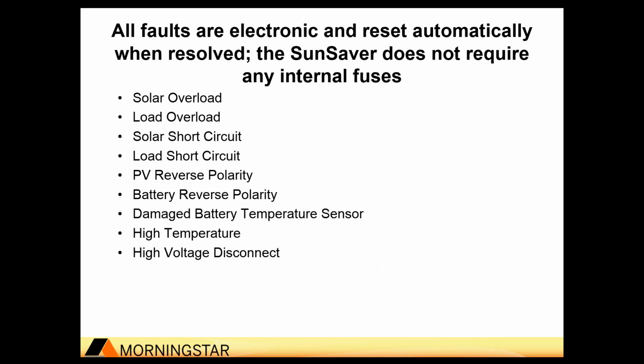Just to detail the electronic protections and emphasize the point that they're all reset automatically. These are conditions that result in a fault of the controller, not some kind of critical error, but a recoverable state. Solar overload, load overload, short circuit protection for both load and solar, reverse polarity on either the battery or the PV, and any kind of high temperature or high voltage disconnect situation. There's really not much that you can do to the Sunsaver during operation to cause an issue, but there are certain few things that we certainly can protect against.